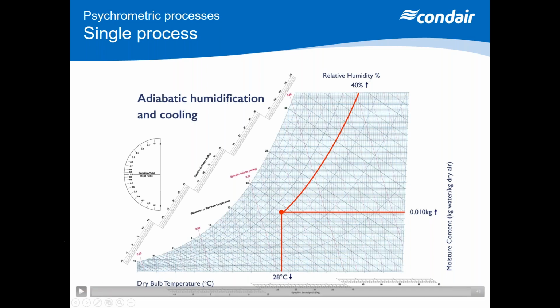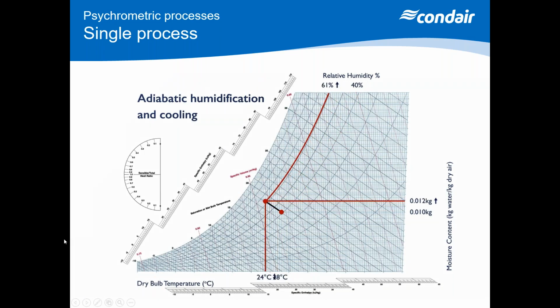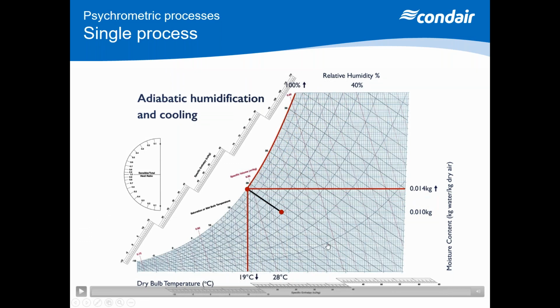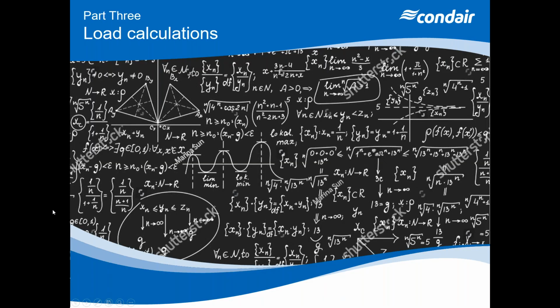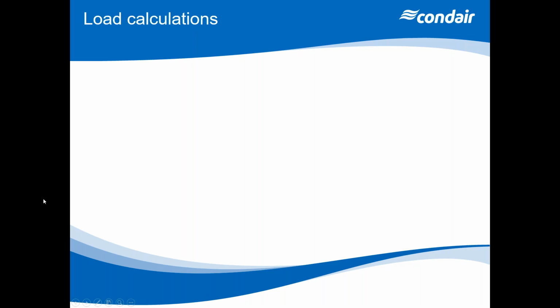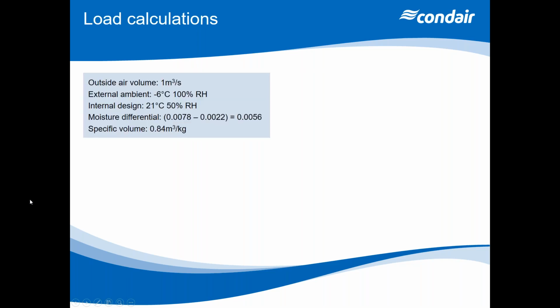So a reminder, we're going to be following that line of enthalpy. Of course, if I draw that line back to my start condition, I'll then humidify up to 21 at 50. Once we've done that, we've decided whether we're going adiabatic or isothermal, we can then look at a load calculation. To do a load calculation, I need to know some data. And the first thing I'm going to want to know is, how much air are we actually humidifying?